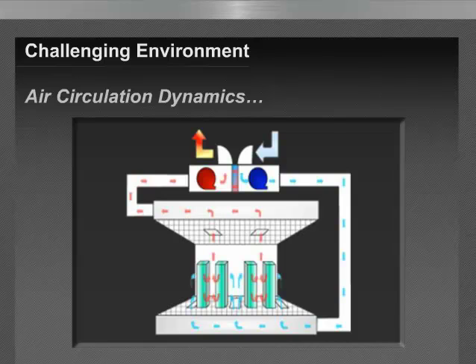But we also look at air circulations. The dynamics of air circulation also present a challenge for reliable smoke detection. So take, for instance, recirculation modes. Let's break it up into two modes, recirculation mode and a growing use of economization mode. So if we look at recirculation modes, with each cycle, smoke enters the HVAC system. And remember that smoke is certainly in an incipient condition. Little buoyancy follows the airstream. First place it's going is to the HVAC system. So once in the HVAC system, it undergoes a degree of scrubbing as a result of filters and an introduction of makeup air contributing to the dilution of smoke.